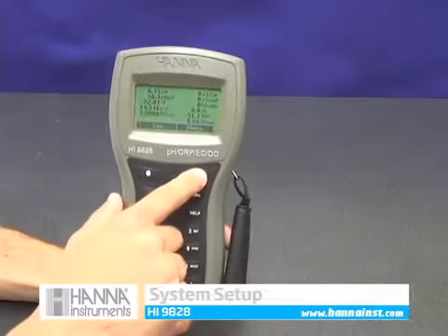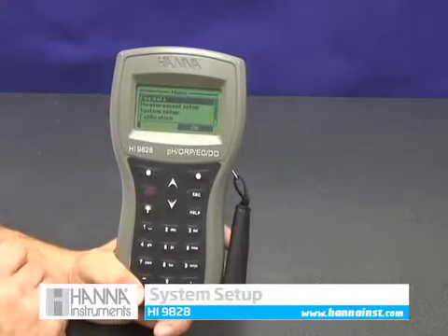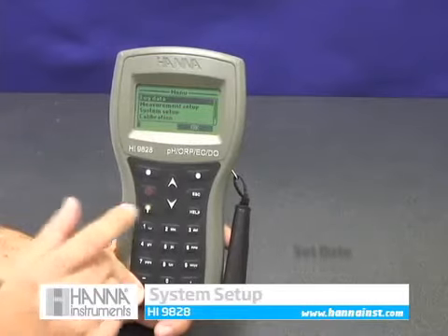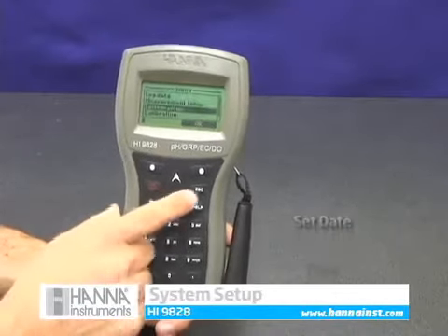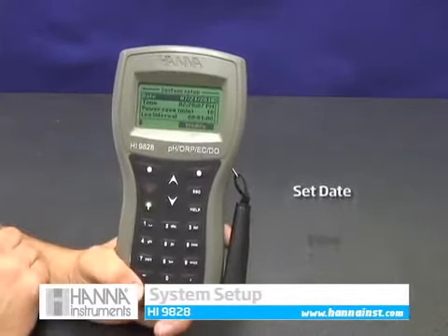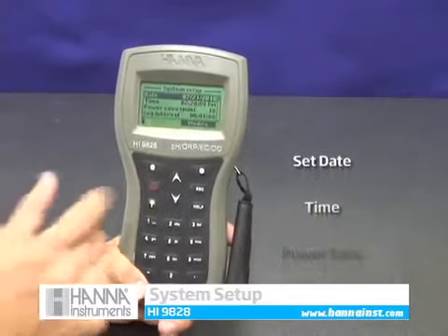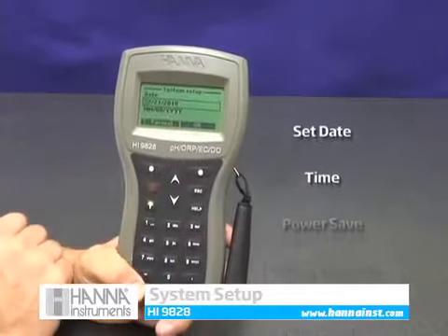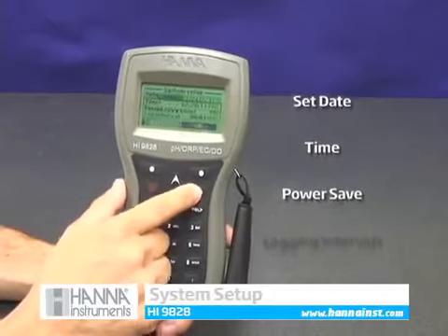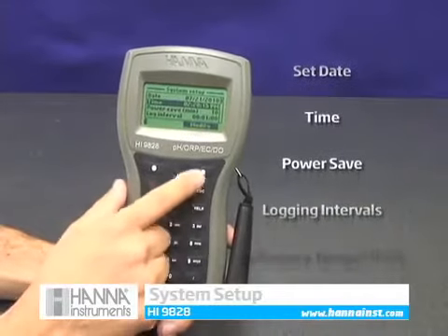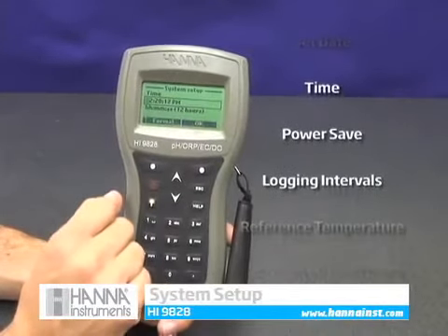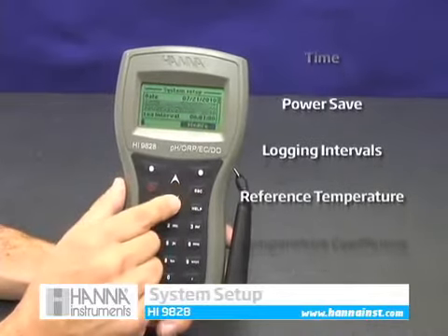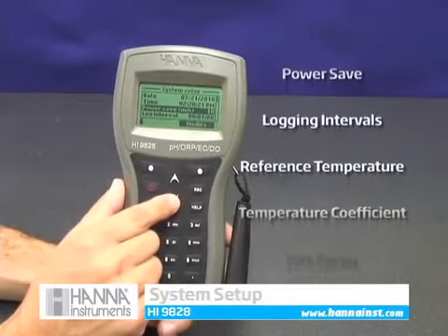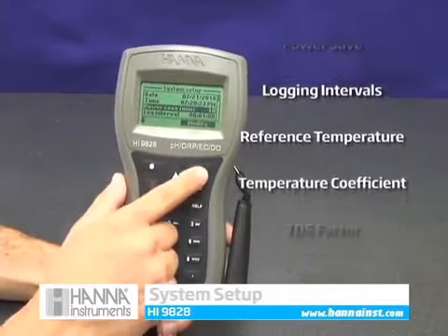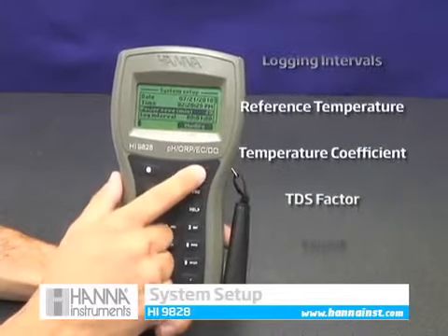The HI 9828's intuitive menu navigation provides users with easy access to everyday options. Let's take a look at System Setup. Access to the main menu screen, System Setup provides the fundamental options for operation and logging. From here you can set the date and time, which will be recorded alongside each of your measurements. The Power Save feature provides the option of turning your meter off when not in use for a specified time. Logging intervals can be easily set between 1 minute and 3 hours.